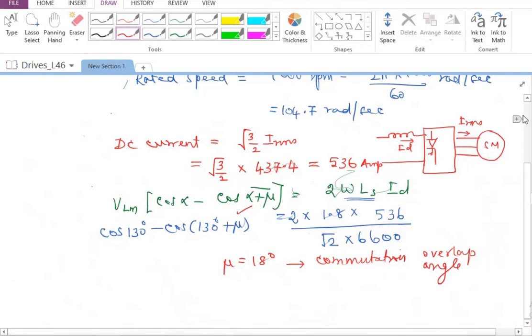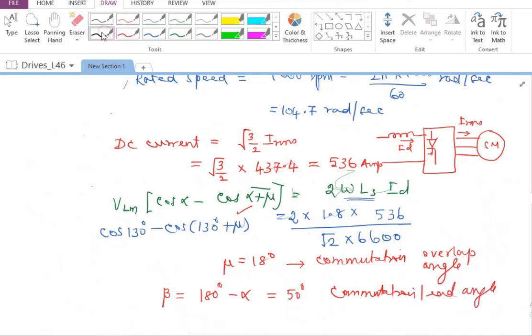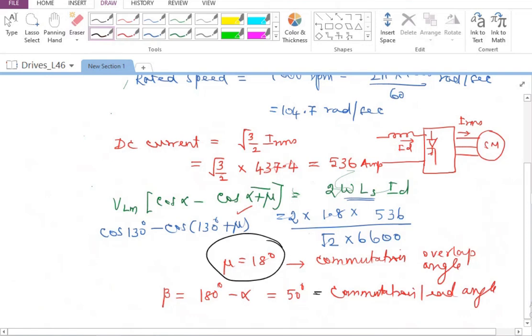Using this, originally the beta value available was 180 degrees minus alpha, which is 50 degrees. This is the commutation lead angle that was available. But out of this, 18 degrees is already eaten away by device number 5 before going off, so the current continues in device number 5 for almost 18 degrees. So 50 minus 18 is what is available for the commutation to take place successfully in the outgoing device. This is the margin angle gamma, which is 50 minus 18, approximately 32 degrees.